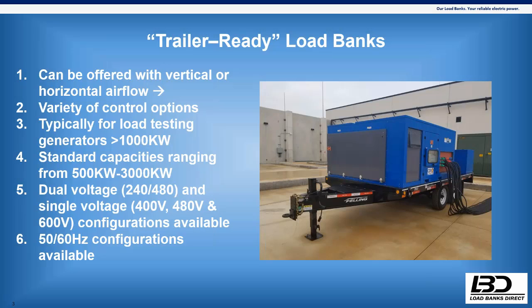Typically, the trailer mounted load banks, this is like the large capacity end of our portable line of load banks. Typically we see these in the 1 megawatt to 3 megawatt range. But I think we've built them as small as 300 kW, but the standard size is 500 kW through 3000 kW. So this is definitely the bigger gear as far as portable load banks are concerned. We also do regular portable units mounted on casters, so roll around units. But depending on where you have to do the load test, how it's going to be used, the trailer mounted option definitely has a lot of benefits over something that's on casters and you have to move around with a fork truck or something to that effect all the time.